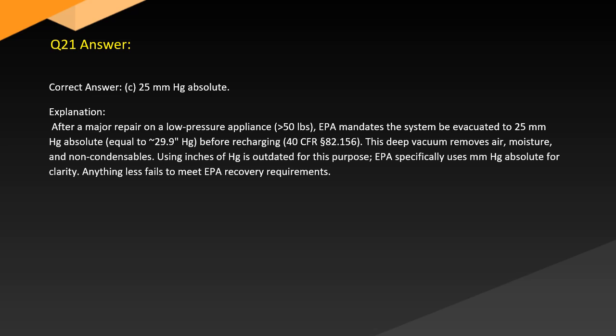Answer. Correct answer, C. 25 mm Hg absolute. Explanation. After a major repair on a low-pressure appliance, 50 pounds, EPA mandates the system be evacuated to 25 mm Hg absolute, equal to 29.9 inches, before recharging, 40 CFR 82.156. This deep vacuum removes air, moisture, and non-condensables. Using inches of Hg is outdated for this purpose. EPA specifically uses mm Hg absolute for clarity. Anything less fails to meet EPA recovery requirements.